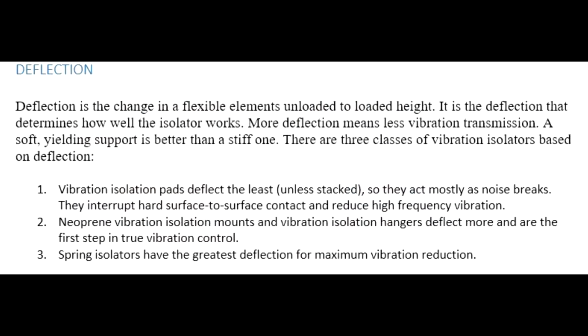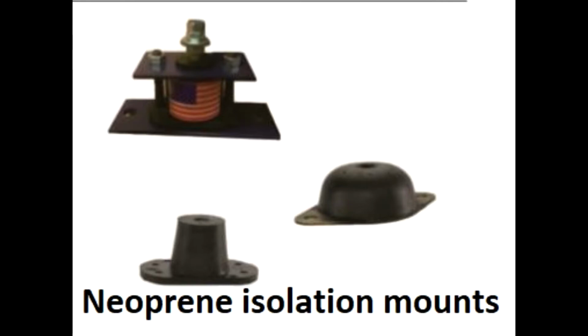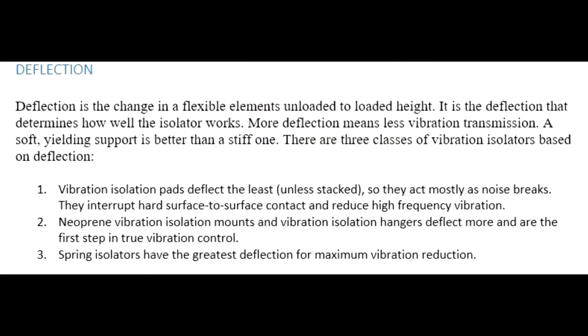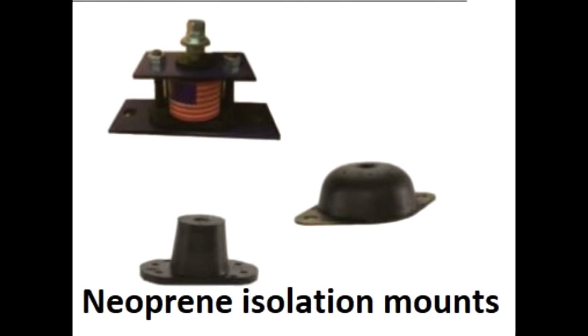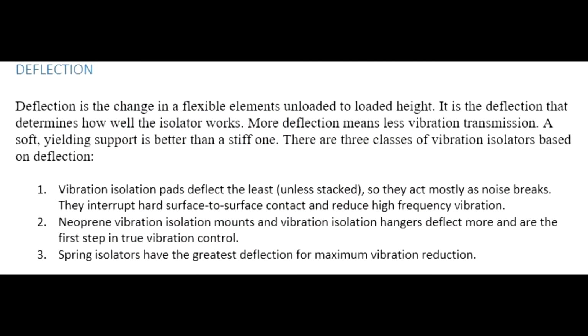Deflection is the change in a flexible element from unloaded to loaded height. It is the deflection that determines how well the isolator works. More deflection means less vibration transmission. A soft yielding support is better than a stiff one. There are three classes of vibration isolation based on deflection. Vibration isolation pads deflect the least, so they act mostly as noise breaks. They interrupt hard surface to surface contact and reduce high frequency vibration. Neoprene vibration isolation mounts and hangers deflect more and are the first step in true vibration control. Spring isolators have the greatest deflection for maximum vibration reduction.